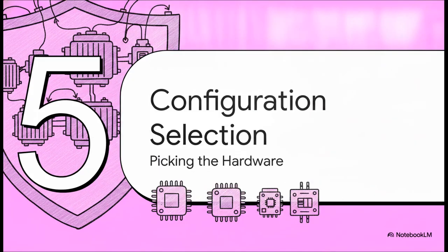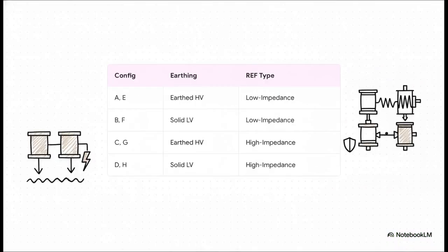Let's wrap this up with Section 5, selecting the right configuration. So how does this translate to ordering your actual hardware? Your configuration letter is strictly mapped to your network. Configurations A, B, E, and F, those are your numerical low-impedance setups. C, D, G, and H are your high-impedance setups. Your choice entirely depends on if you're protecting the high or low voltage side, and most importantly, whether your CTs are forcing you into that low-impedance bucket.